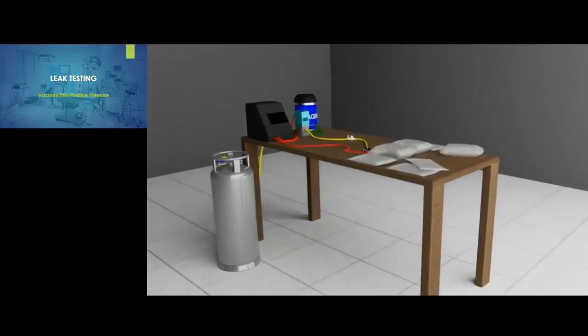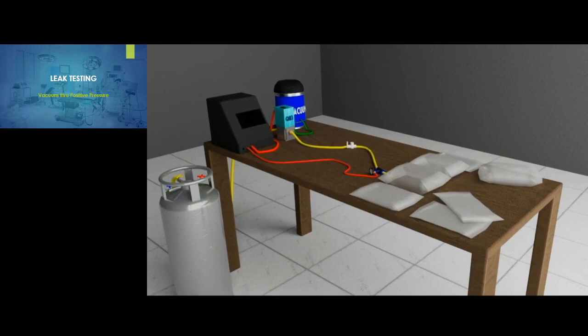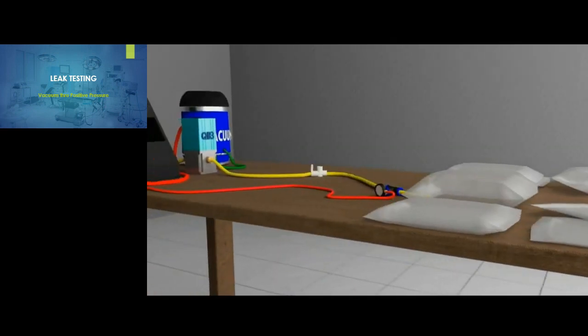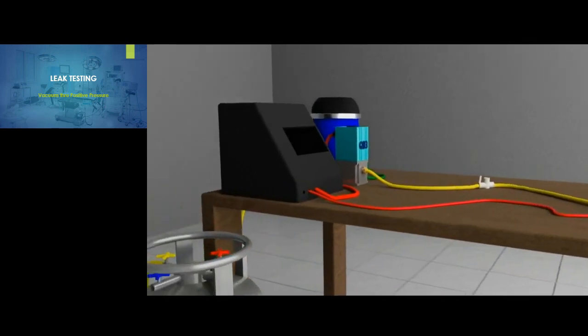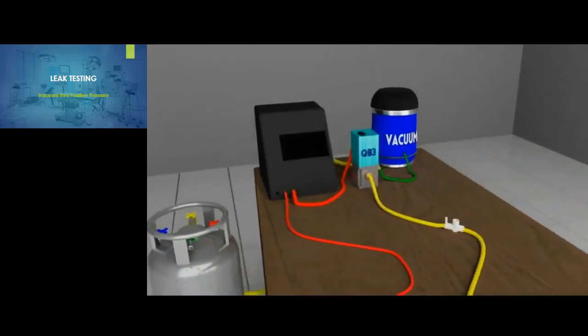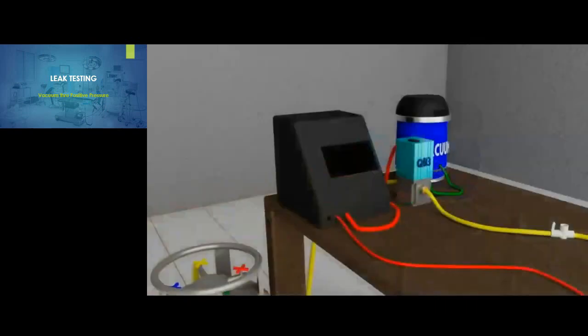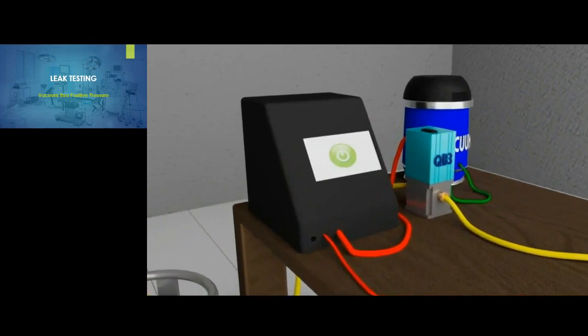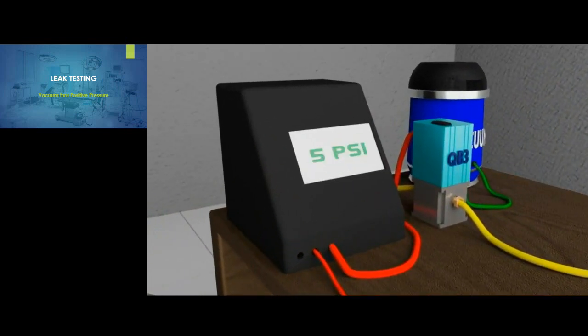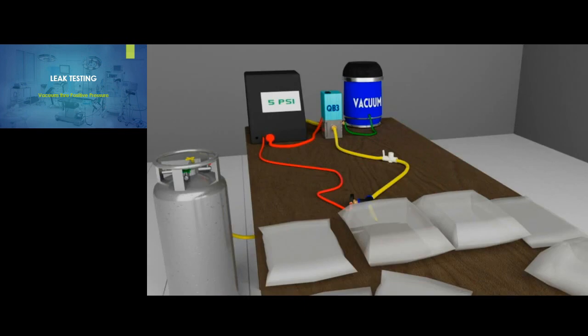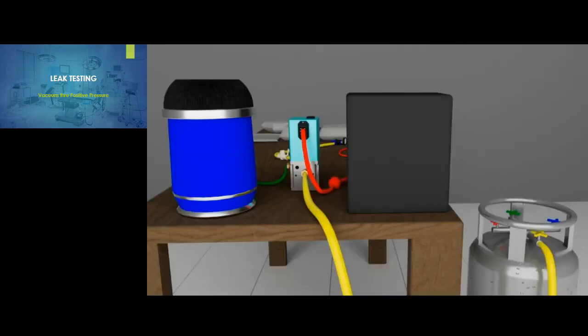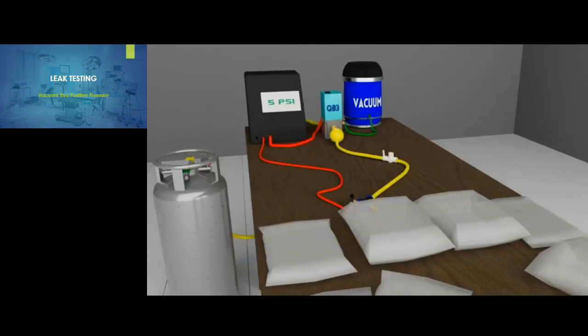Quality control is imperative in medical equipment manufacturing. Producing IV bags is no exception, so they are tested before they go into use. In this example, we use a pressure regulator to assist testing an IV bag for leaks. First, a signal is sent to the QB3 to command the amount of pressure to be applied to the bags. The regulator applies positive pressure to fill the bag with the test gas.